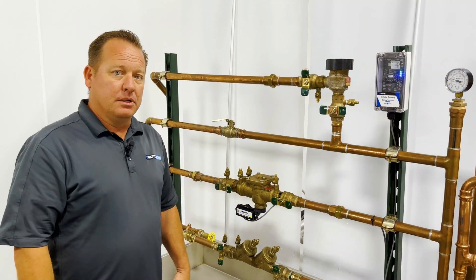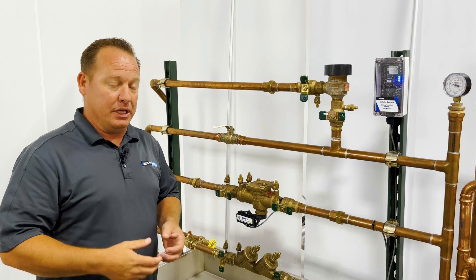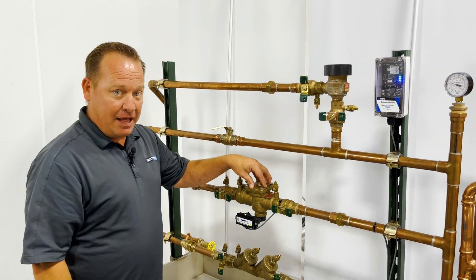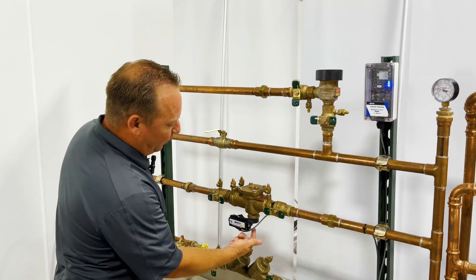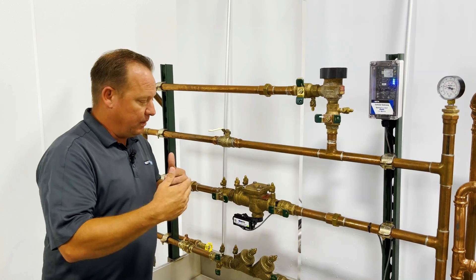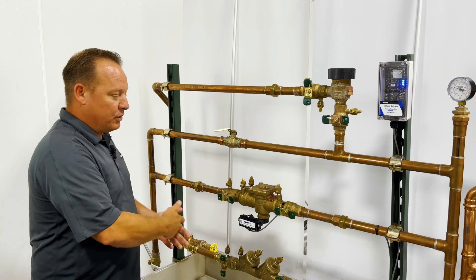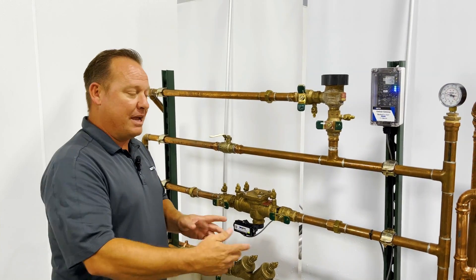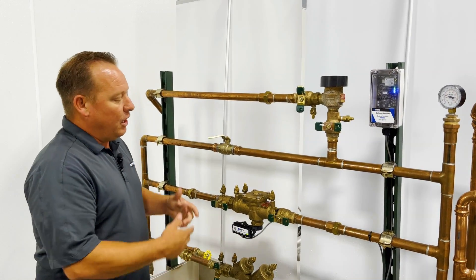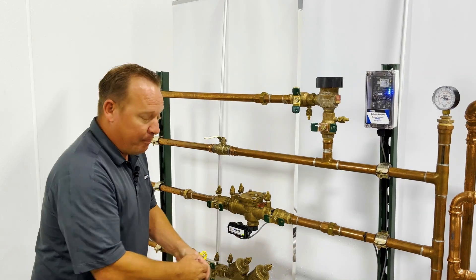So why would you want to monitor a backflow preventer? If you work with backflows, you'll notice right away that on any ASSE 1013 backflow there's always going to be a relief valve. These devices are designed to fail — if we lose upstream pressure this is going to dump water, if we have major back pressure downstream this will cause the device to dump, and if we have any internal issues this device is going to dump.